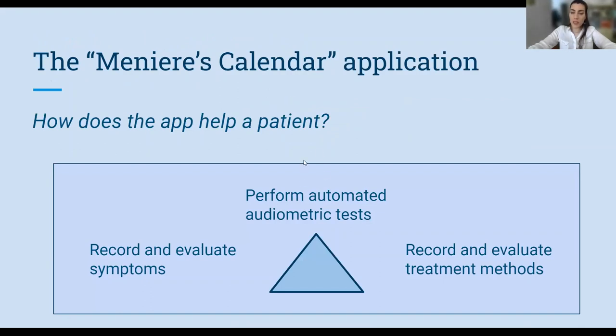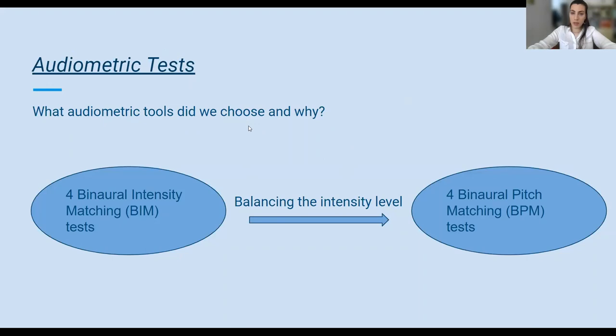So how does the app help a patient? First of all, it replaces the classic paper diary — the patient can record and evaluate symptoms and treatment methods. The other usage of the Meniere's calendar application is the performance of automated audiometric tests. The task was to find self-tested methods that are reliable, and after extensive research we ended up with a series of binaural tests: four of intensity matching followed by four of pitch matching. The main idea is to overcome problems like device calibration by measuring the hearing ability of the impaired ear compared to the unaffected ear, as Meniere's disease is mostly unilateral.